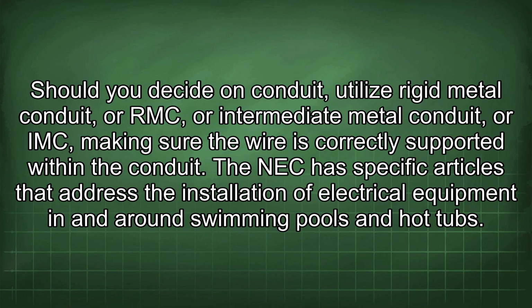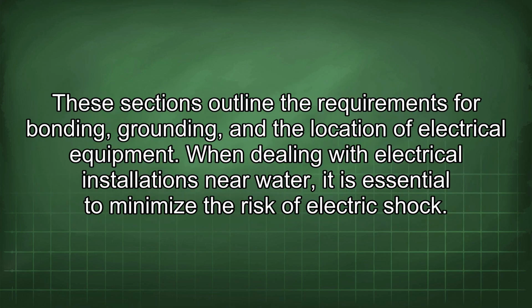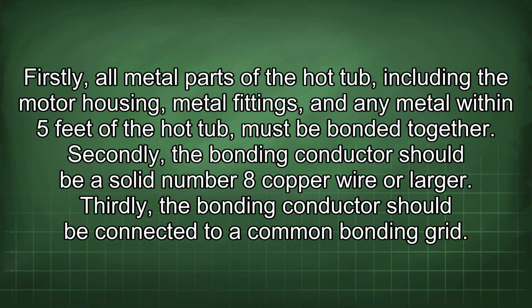The NEC has specific articles that address the installation of electrical equipment in and around swimming pools and hot tubs. These sections outline the requirements for bonding, grounding, and the location of electrical equipment. When dealing with electrical installations near water, it is essential to minimize the risk of electric shock. Firstly, all metal parts of the hot tub, including the motor housing, metal fittings, and any metal within 5 feet of the hot tub, must be bonded together.